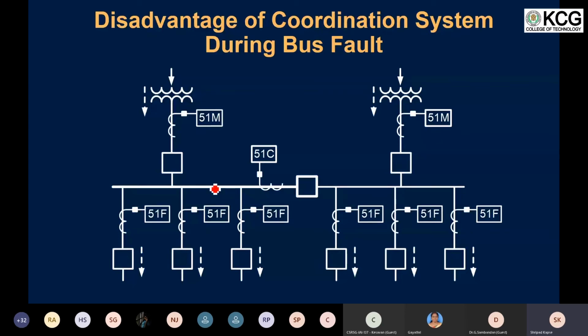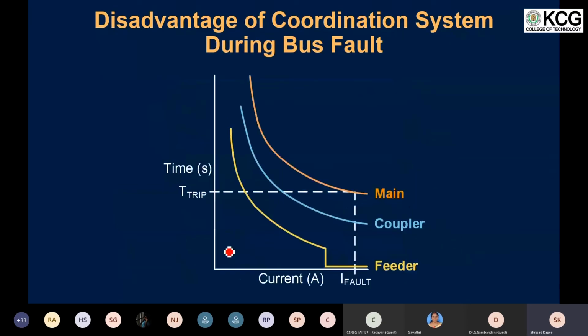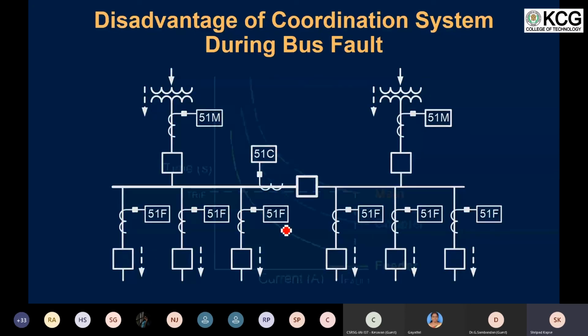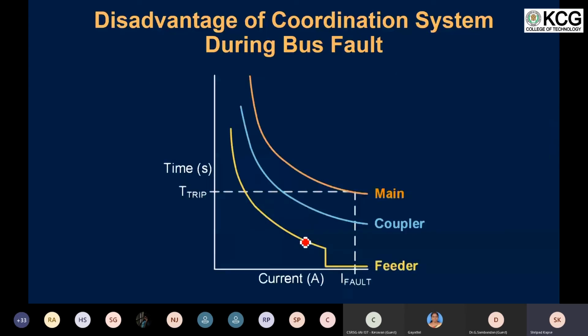If you look at a typical industrial system or a generation system, you would find two incomers and one bus coupler. These incomers feed power to the outgoing feeders, which may be a tie feeder, a motor feeder, or some load. In any power system, in order to maintain selectivity and sensitivity, the relays used to protect these feeders are time coordinated. For the outgoing feeder relays, the operating time is much faster, and for the bus coupler and the main incomer relay, it is slightly slower. This is just to maintain selectivity for the fault.